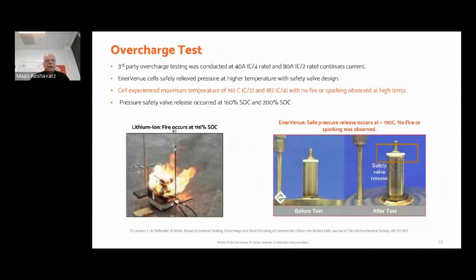Overcharge is very important. The battery was overcharged under two different conditions, 40 amp, C/4 and C/2. When you overcharge, obviously you generate heat, because the current has to go somewhere. The temperature reached around 200 degrees or so, but then again no fire or explosion or anything was seen. It just got hot and released the gas. There is a safety valve in these batteries, as shown in the bracket here on the right-hand side. At a certain temperature and pressure it releases the gas.